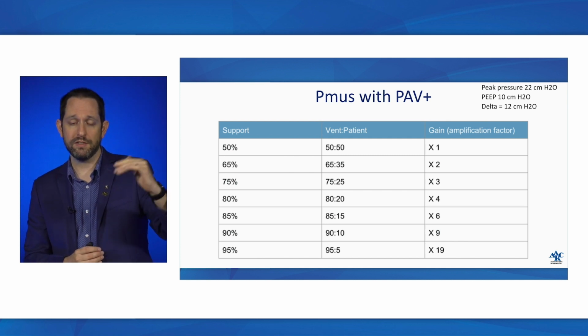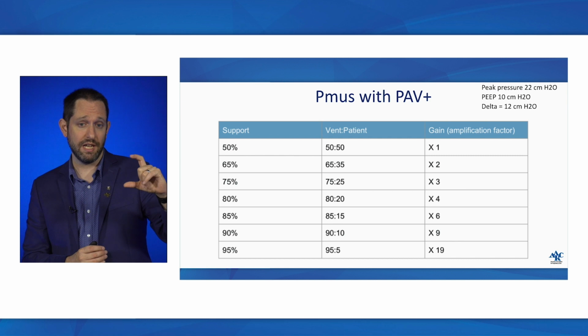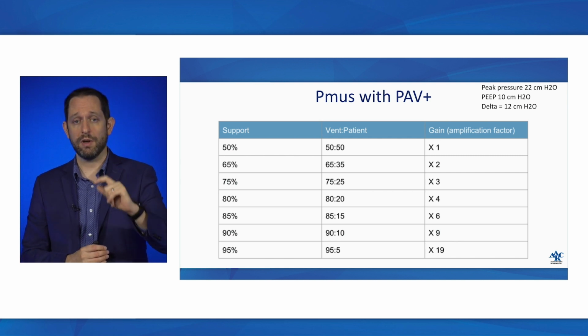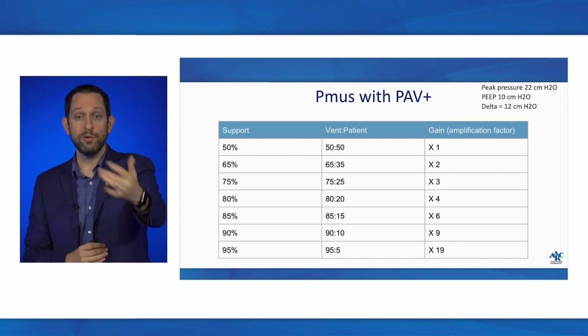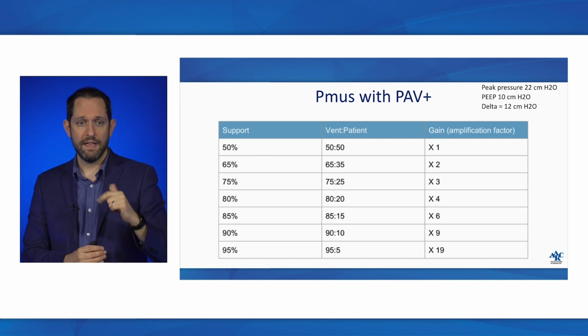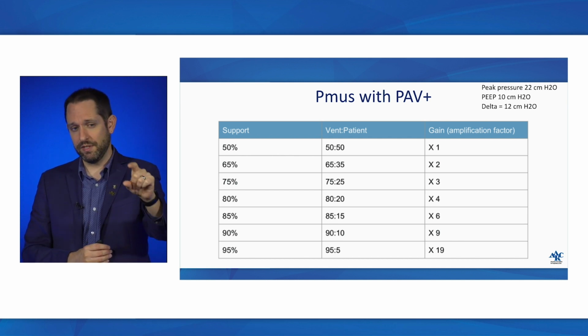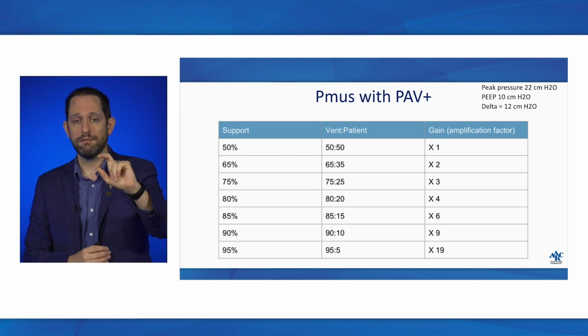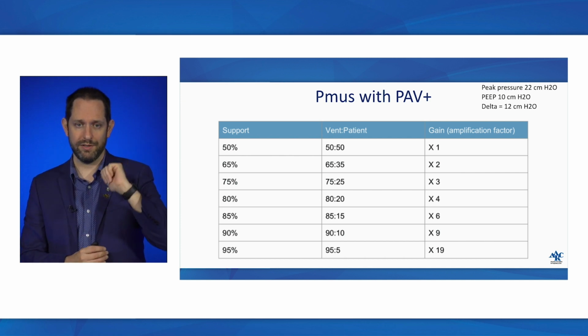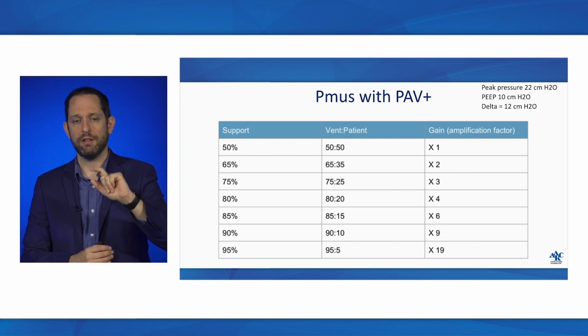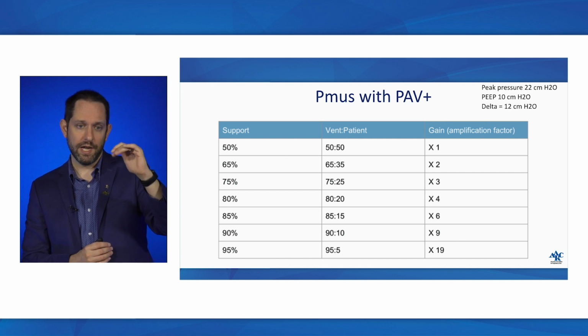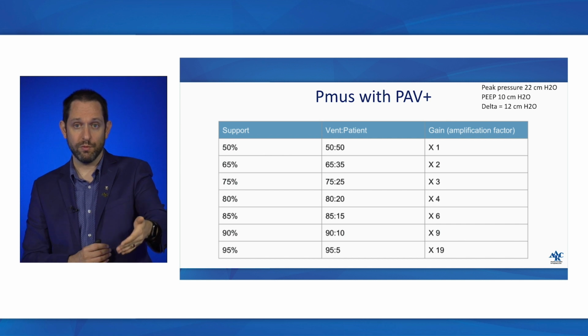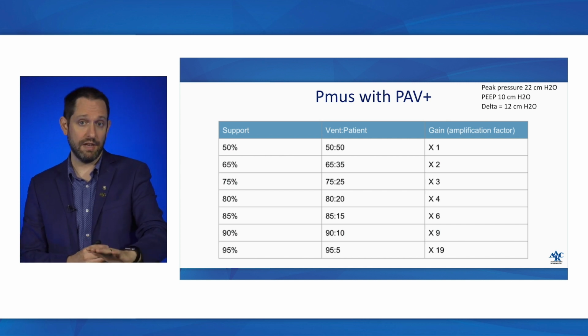But going from 50 to 65, so a jump of 15%, changes the gain factor by 1, meaning the ventilator is doing 2 times the work when you go to 65. If you go then up 10% from 65 to 75%, the ventilator is now doing 3 times the work of the patient. At 80%, the ventilator is doing 4 times the work of the patient. So as you can see, as you go higher, you have to make smaller changes to make that large impact in terms of work of breathing taken over by the ventilator.